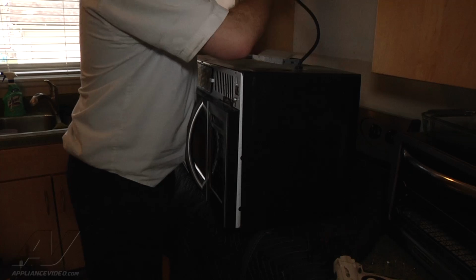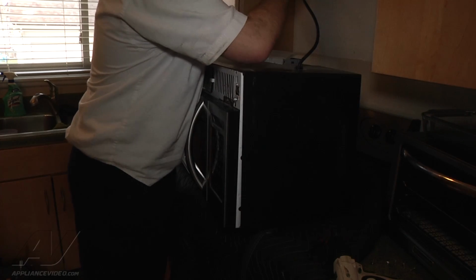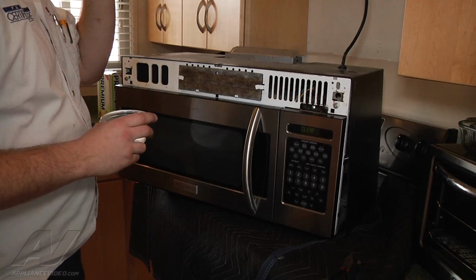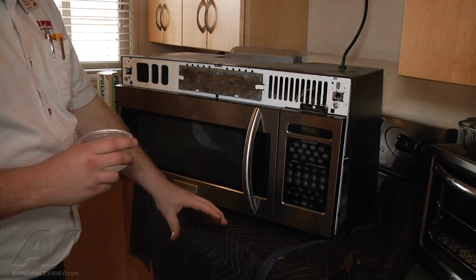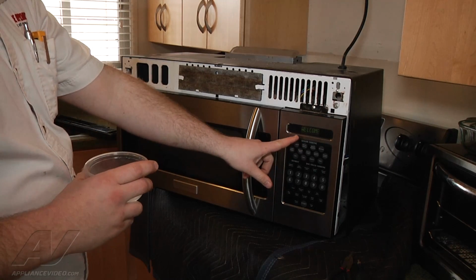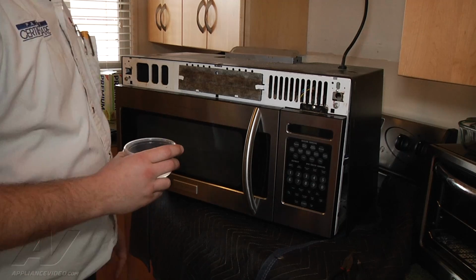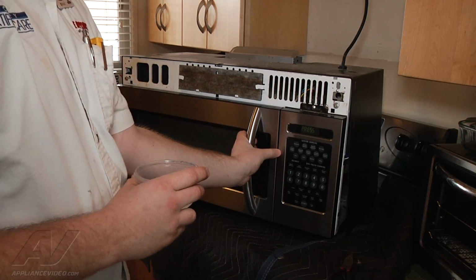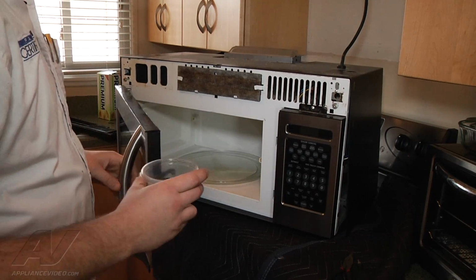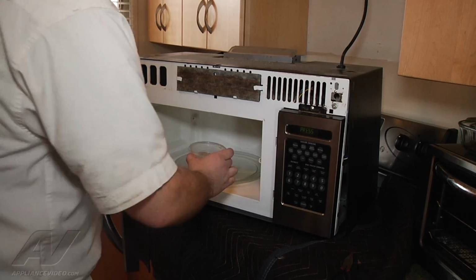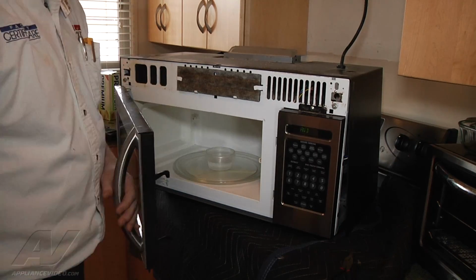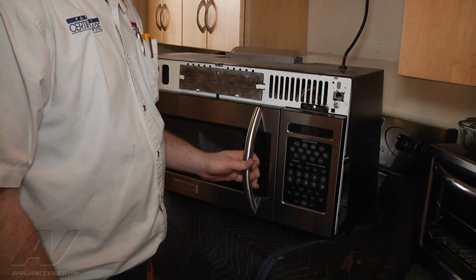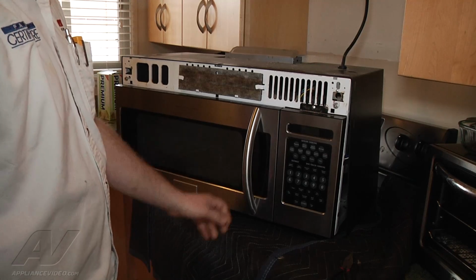So we got that back on there. We're going to plug it back in with our new fuse and run it and see what happens. We replaced the fuse, and you can see we do have power back to the control panel here. Like I said, we still need to run it and see if anything's causing the fuse to blow. So we're going to put a small bowl or cup of water inside of here before we run it to see if it's heating up the water and everything.